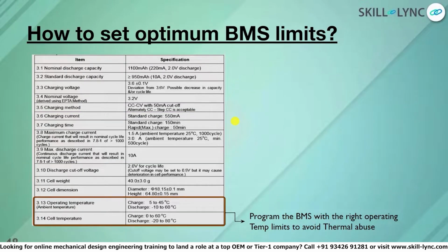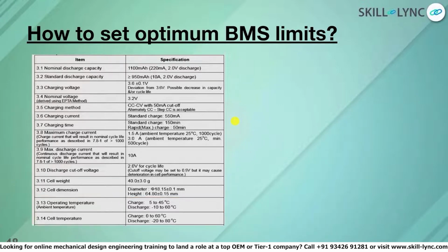Depending on these C rate conditions, we program the BMS accordingly from the cell point of view, and also from the cell operating point of view and cell temperature operation. The BMS is actually to be designed by considering the cell's safe operating limit. If that is not taken into picture properly, the whole BMS design goes wrong. This has to be taken care of while designing a BMS, which leads to better overall pack efficiency, and safeguards the pack in a much better way, because we know the cell better and test it as much as possible, so the BMS is programmed accordingly, making a better battery pack always.